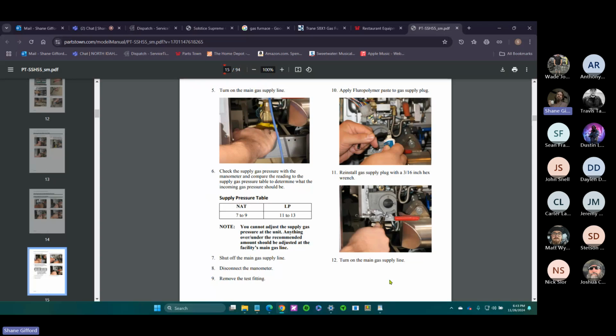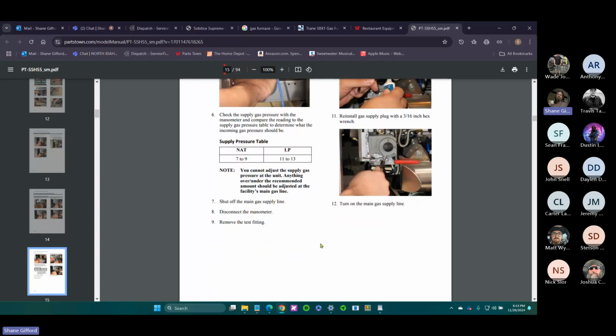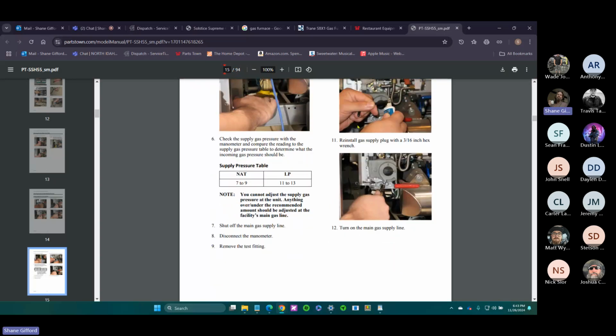There was a gas station out in Blackfoot, I don't remember, that little fast food chicken place. That's exactly what happened with their Henny Penny. Their gas regulator had failed, and there was so much pressure behind the valve, it was shooting out giant flames, at 8 inches water column instead of 4. So big problem there. Sometimes the problem isn't even with the fryer or the cooking appliance. Sometimes the pressure to your appliance is just too low or too high.